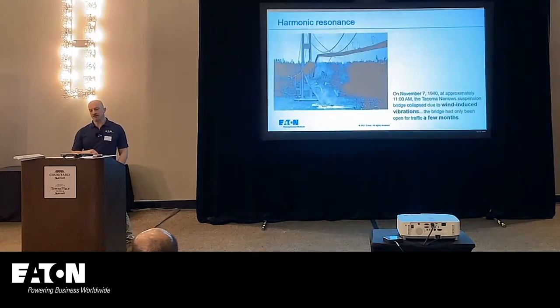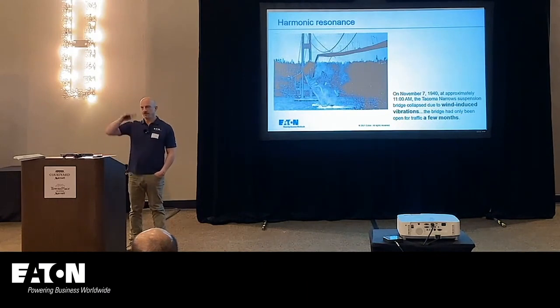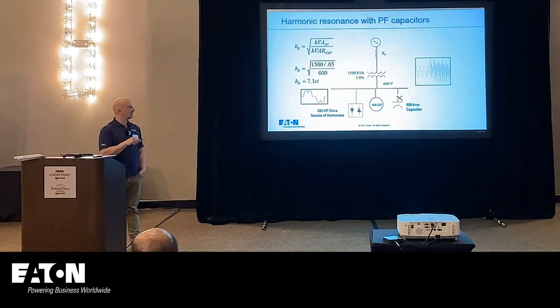So resonance is a really important issue. You guys ever see the Tacoma Narrows Bridge? It oscillated and it ripped itself apart. If you put capacitors on a power system, basically they will resonate at a certain frequency. And in this case, if they resonated around the 7th harmonic and I have a 6-pulse drive, do I have a source of 7th harmonic? Yeah. So I'm pushing 7th harmonic out, and let's say I push out 10 amps of 7th harmonic current. Between these two things resonating, it may get up to 1,000 amps of 7th harmonic current.